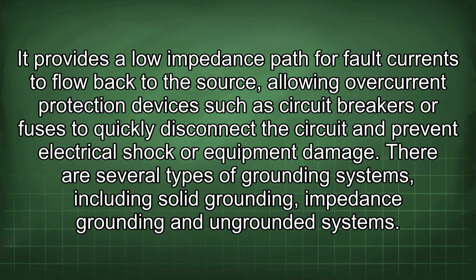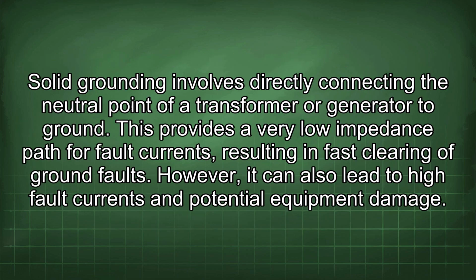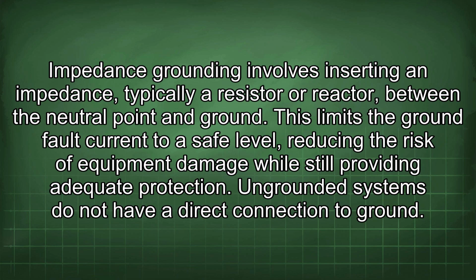There are several types of grounding systems, including solid grounding, impedance grounding, and ungrounded systems. Solid grounding involves directly connecting the neutral point of a transformer or generator to ground. This provides a very low impedance path for fault currents, resulting in fast clearing of ground faults. However, it can also lead to high fault currents and potential equipment damage. Impedance grounding involves inserting an impedance, typically a resistor or reactor, between the neutral point and ground. This limits the ground fault current to a safe level, reducing the risk of equipment damage while still providing adequate protection. Ungrounded systems do not have a direct connection to ground.